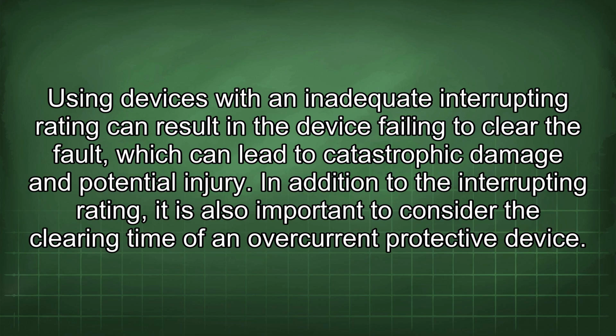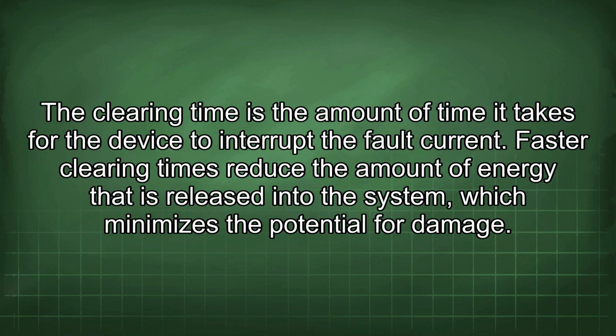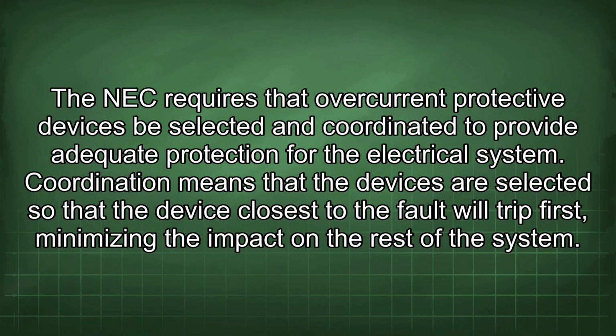In addition to the interrupting rating, it is also important to consider the clearing time of an overcurrent protective device. The clearing time is the amount of time it takes for the device to interrupt the fault current. Faster clearing times reduce the amount of energy that is released into the system, which minimizes the potential for damage. The NEC requires that overcurrent protective devices be selected and coordinated to provide adequate protection for the electrical system. Coordination means that the devices are selected so that the device closest to the fault will trip first, minimizing the impact on the rest of the system.